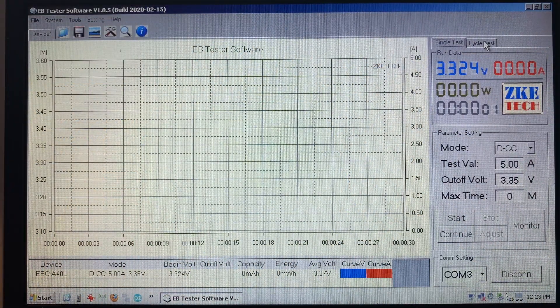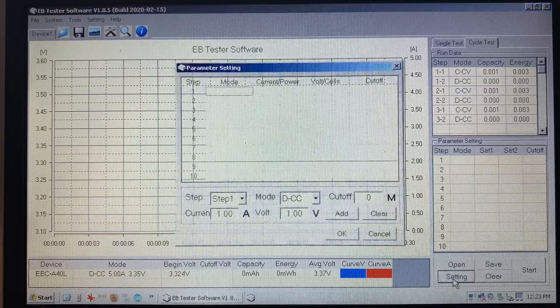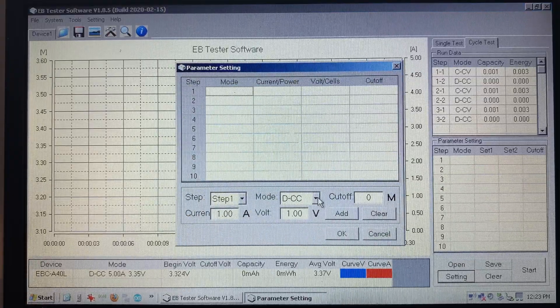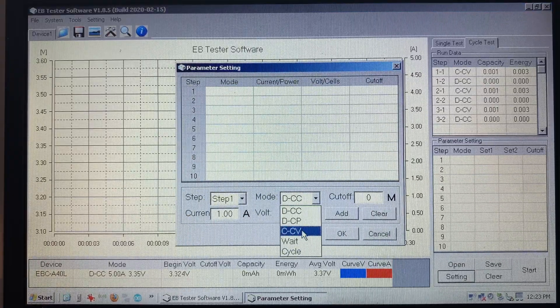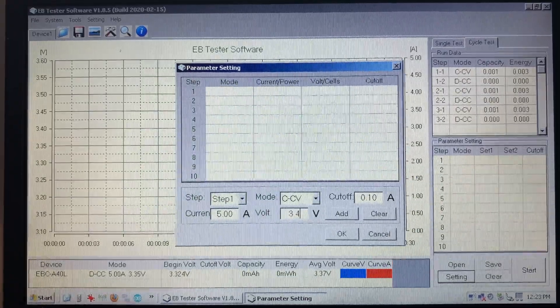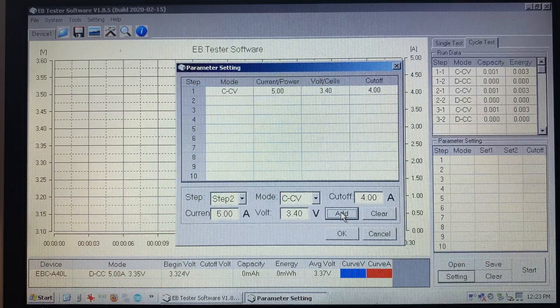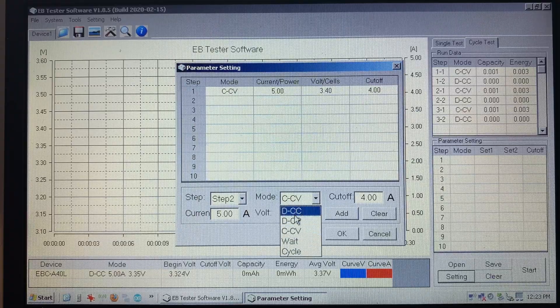Previously I was showing you how to run a single test from the PC software and now I'll show you how to set up a recipe to run a cycle test. Click on settings and here we're going to do a constant charge at 5 amps to 3.4 volts and we'll do the current cutoff at 4 amps and click add. So that's our first line in the recipe.